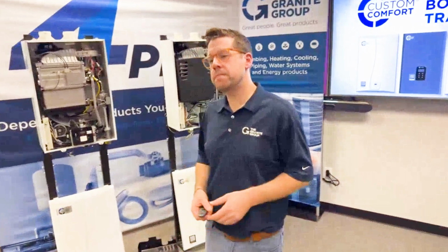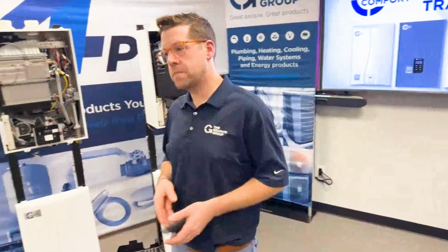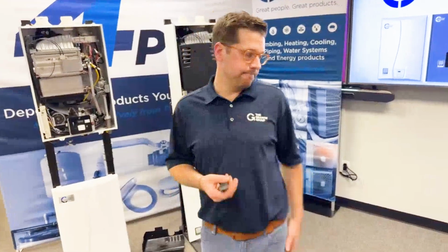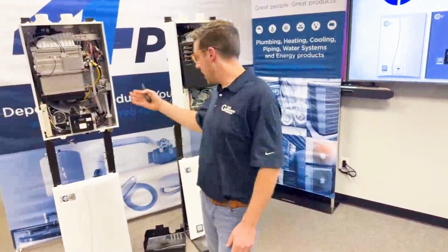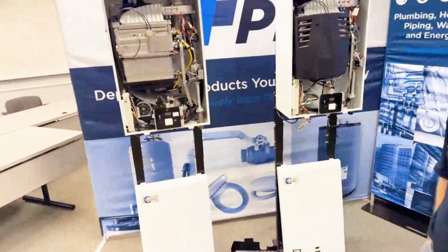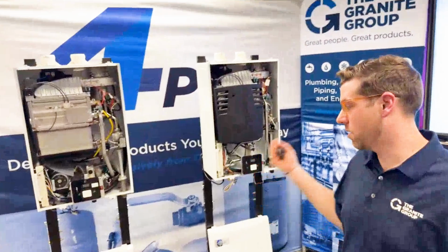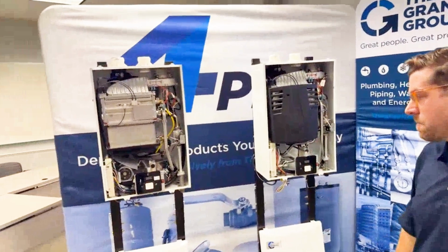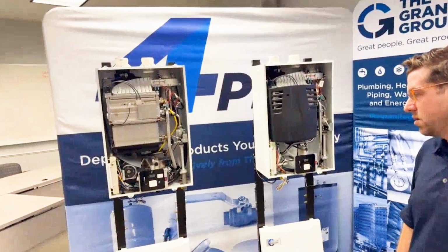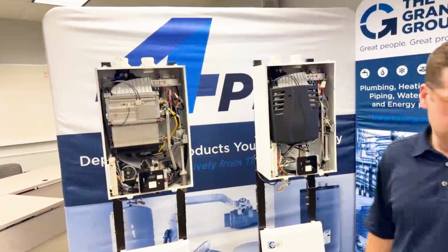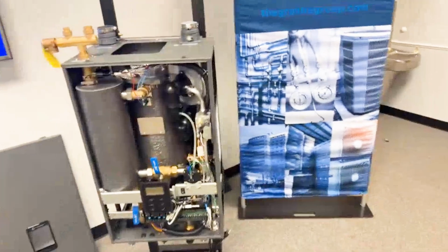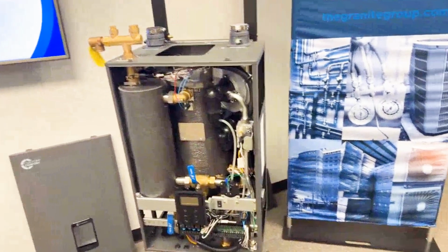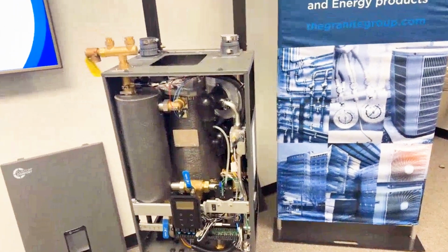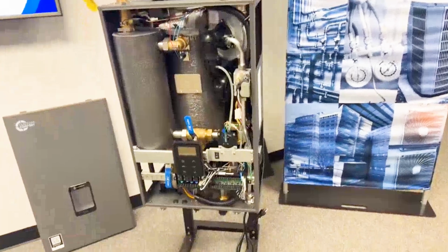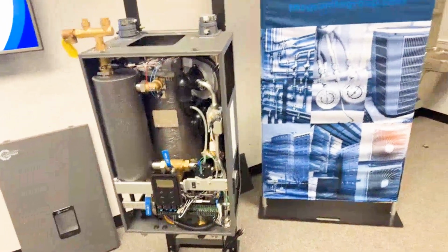Will we still need additional strainer screens? So I would say on the combi and the heat only, not a bad idea to throw a Y strainer on there. Again, the dirt separator with a magnet, never going to be a bad thing to include those in your system. On the fire tube combi, we've got some filters built in. I would push more for a magnetic dirt separator on the fire tube versus an additional Y strainer or something like that, with the filters that are built into it.